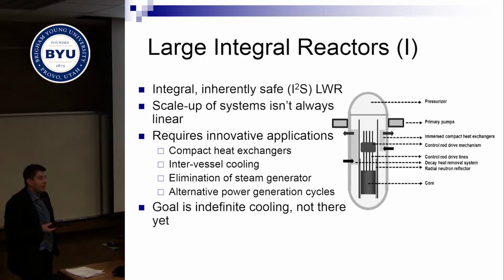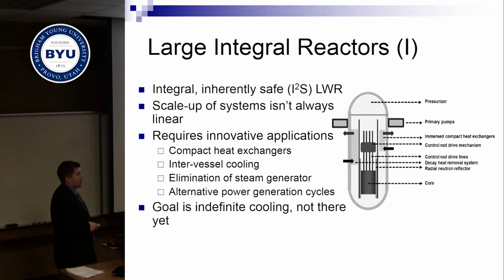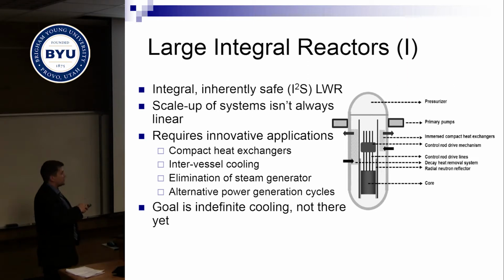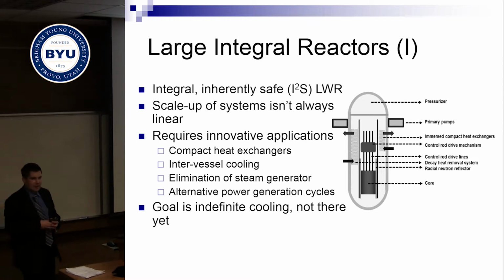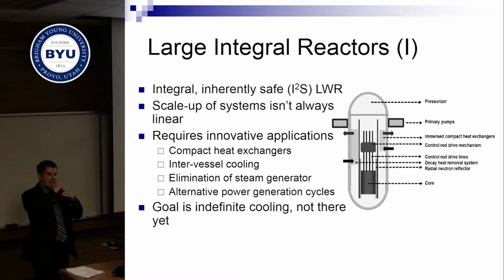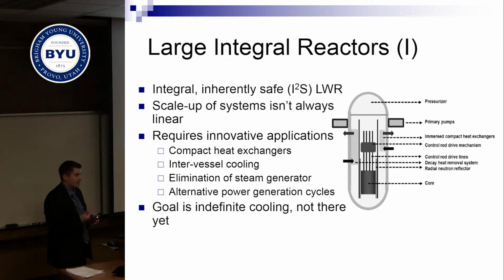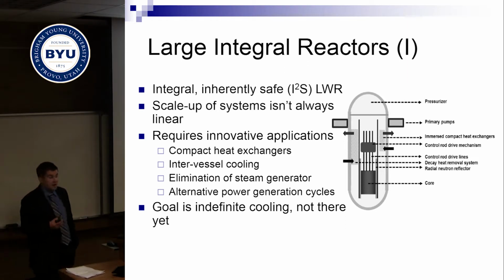We had to go to compact heat exchangers and different designs nobody has done before in nuclear. We actually don't boil inside the reactor; instead we just have a compact heat exchanger — like a printed circuit heat exchanger. It's basically a bunch of metal plates etched with very small semicircular channels, about 1 millimeter across, stacked on top of each other. You have thousands of these channels that the water goes through, designed for laminar flow, very effective because it's surrounded by metal, alternating hot and cold on the plates, so it's a very short heat transfer distance and a very effective heat exchanger.